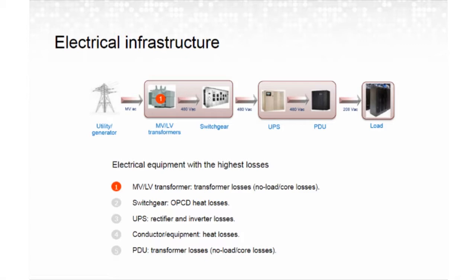Designers have the option of reducing the quantity of transformers and thus increasing their size, or designers can distribute transformers throughout the building to reduce feeder costs and thus feeder losses. So essentially, you can either have more transformers that are smaller or fewer transformers that are bigger. Because transformers are a substantial portion of system losses, the topology of the system chosen should take transformer efficiency into consideration.